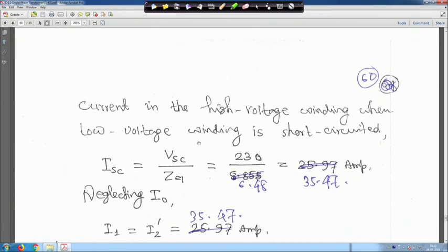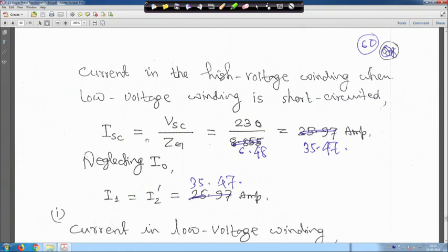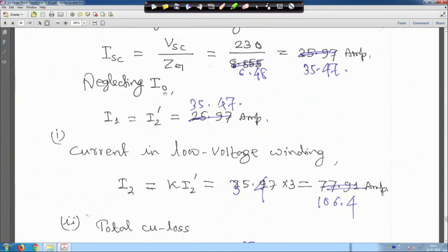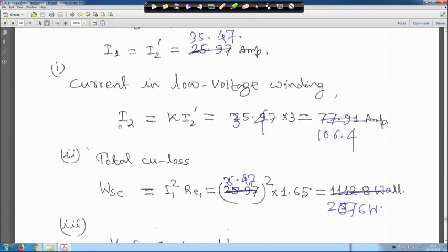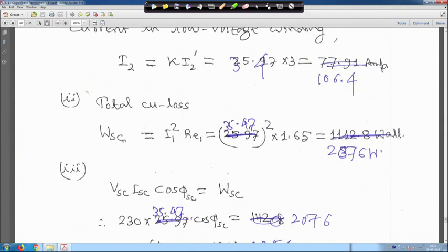Short circuit current I_SC equals V_SC divided by Z_E1 = 230 / 6.48 = 35.47 ampere. Neglecting I_0, I_1 equals I_2' equals 35.47 ampere. Current in the low voltage winding: I_2 equals k × I_2' = 3 × 35.47 = 106.4 ampere.